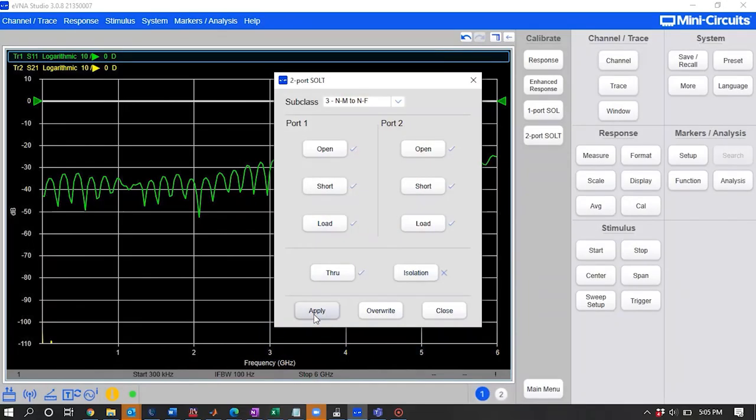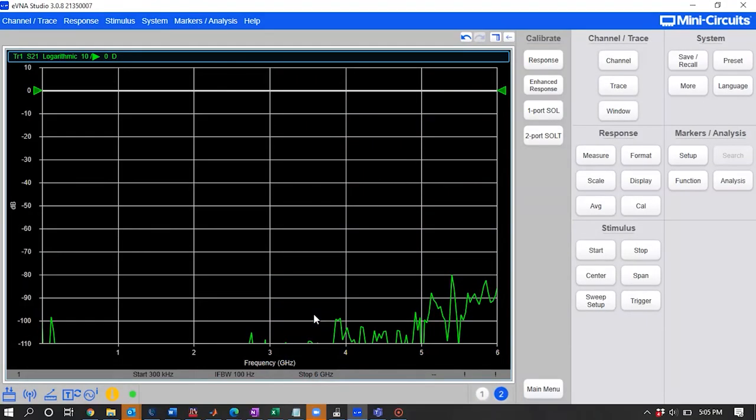Once all the measurements are completed, apply the calibration and save the calibration state in the system menu for future recall. Now your calibration is complete and you are ready to measure your DUT.